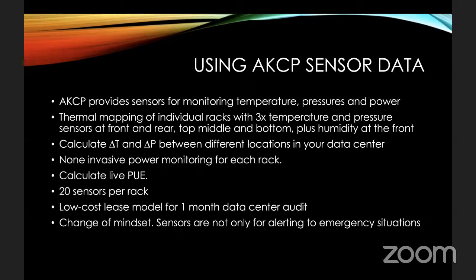So you have a new client in a co-location data center, but you can't onboard that new client because you have no more cooling capacity. You've got to buy more CRACs. If you can run your data center more efficiently, you can take on that client with the same CRAC units that you already have, because you can utilize the cooling efficiently and make sure that it's reaching where it's needed at the right time. But you cannot do this just by guesswork. You cannot do it through a CFD model, because a CFD model is just assumptions. You need the sensors in order to be able to actually fine-tune your system.